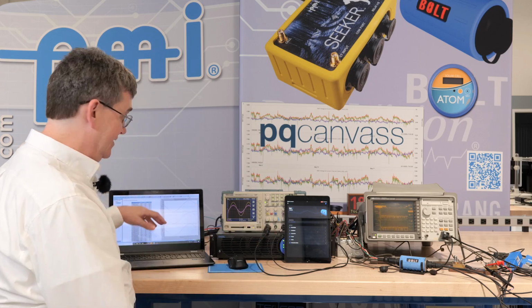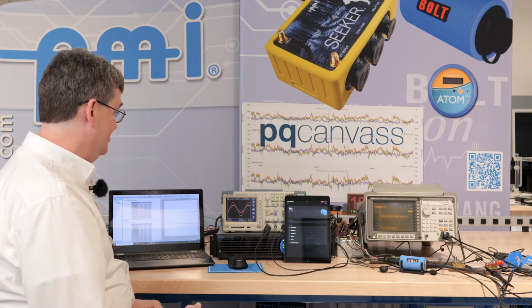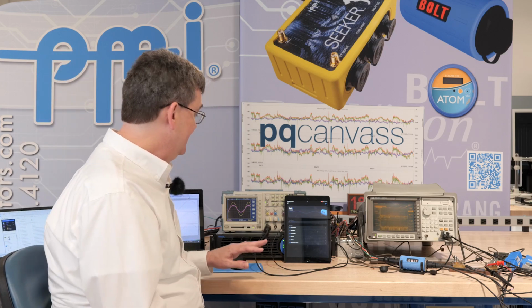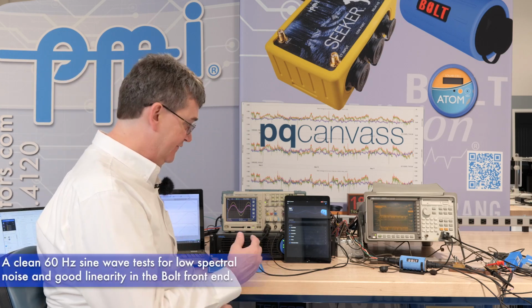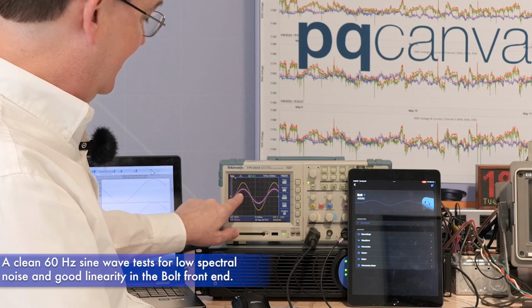So the first test is a 60 Hz sine wave. This should be a clean sine wave, should have no harmonic content at all. So in theory, the THD should be 0 for voltage and for current. We can see it looks like a clean sine wave on the scope.